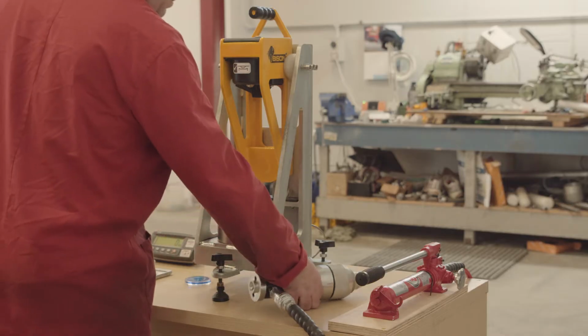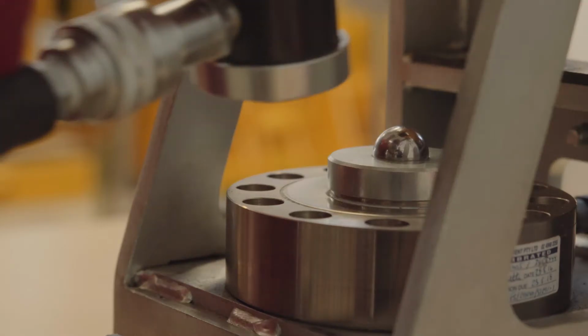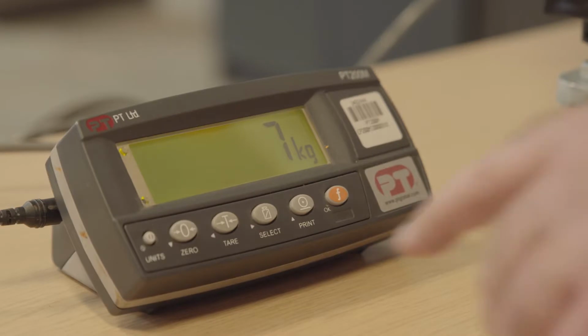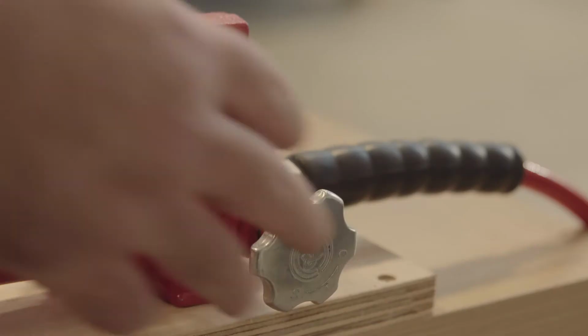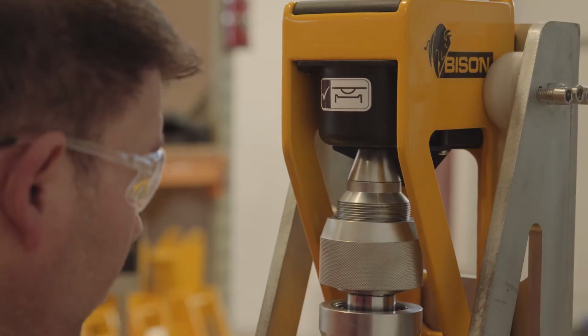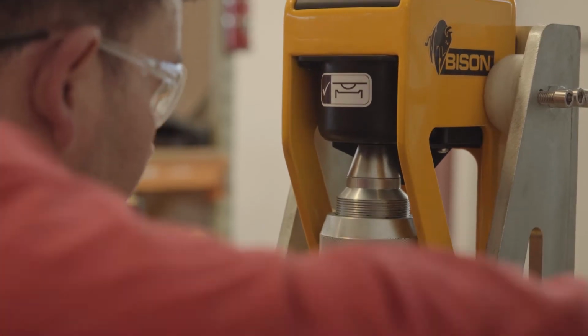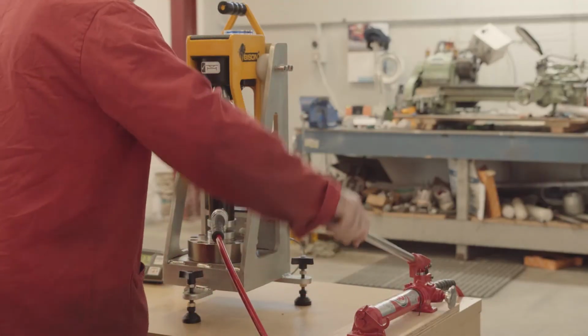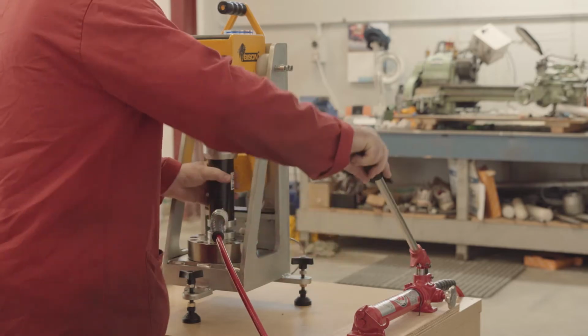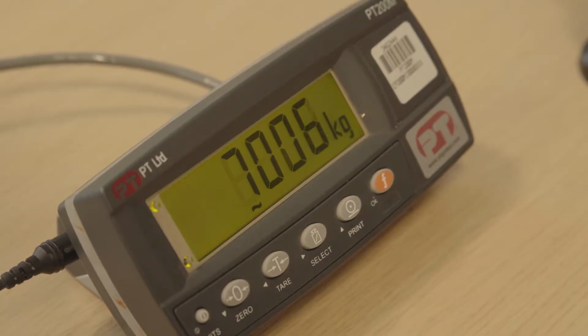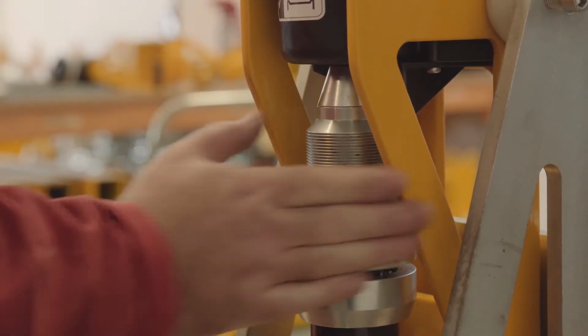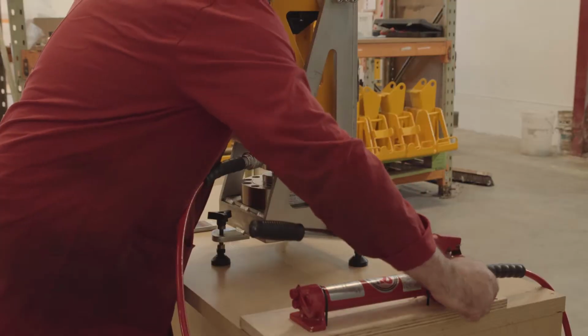Next, apply load to the scale. Place the hydraulic cylinder carefully on the reference load cell and zero the reference indicator. Close the valve and pump the hydraulic hand pump until the cylinder is engaged with the scale. When you have confirmed that everything is safe to proceed, slowly pump the handle and watch the load increase on the reference indicator. Keep pumping until the load reaches about 8,000 kilograms. Then lock the collar on the hydraulic cylinder and release the hydraulic pressure.